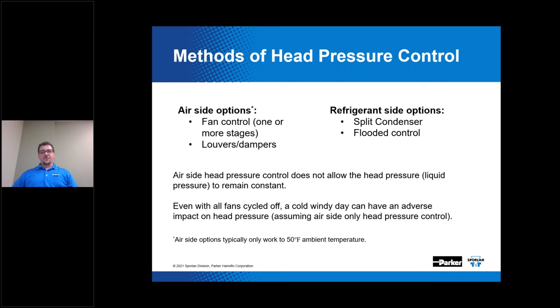Another disadvantage is that even with all fans cycled off, a cold windy day can have an adverse impact on head pressure if you are only deploying air side control. System designers very frequently choose a combination of air side and refrigerant side head pressure control, because air side alone typically does not work well at really low ambient temps. I'll be focused on the refrigerant side methods of head pressure control for the rest of the discussion.